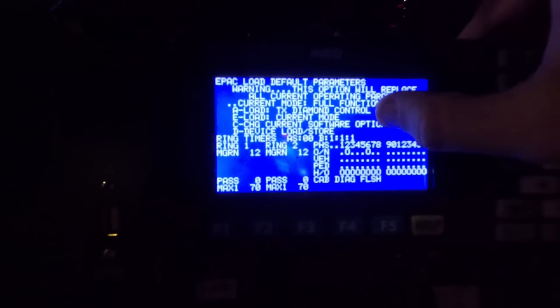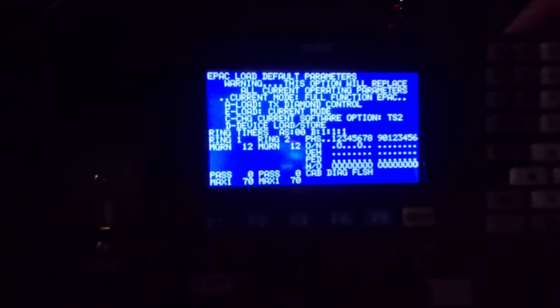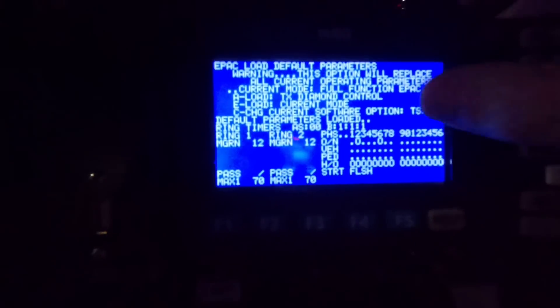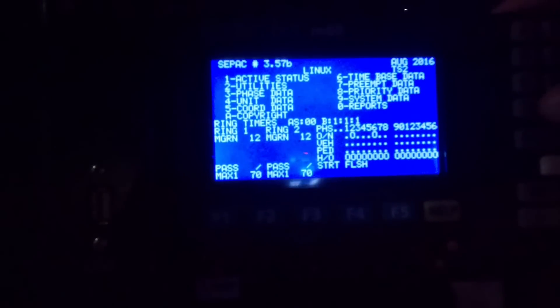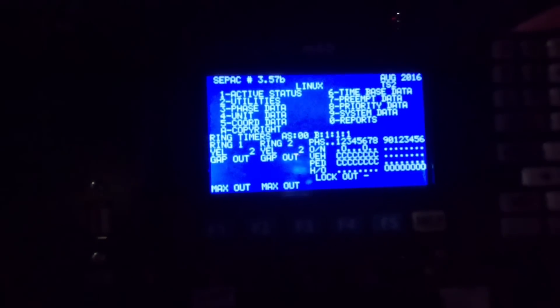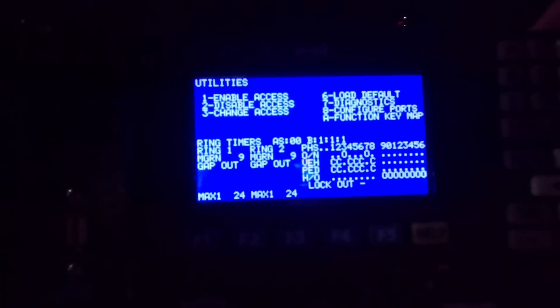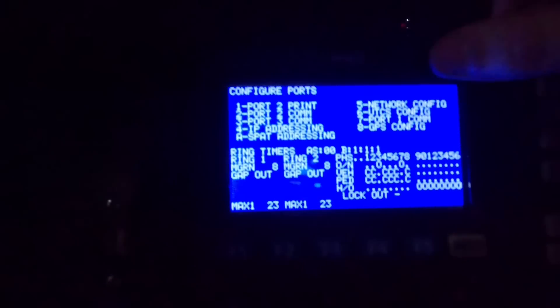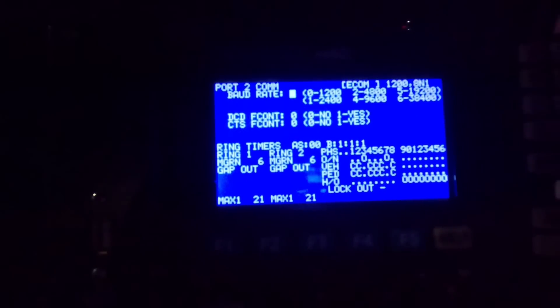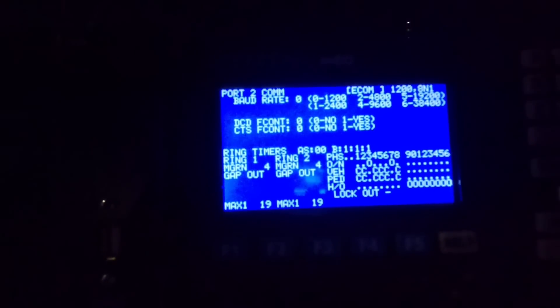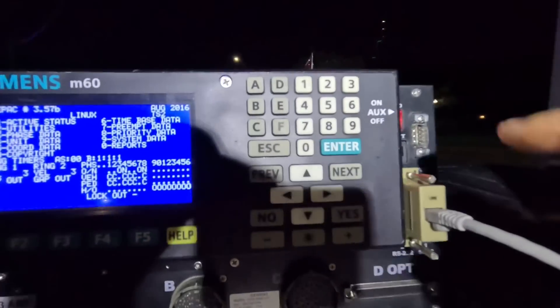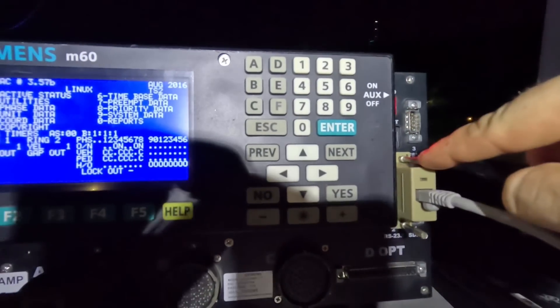I need to press Utilities, you'll see six over here, we're going to hit Load Default, and then Load Current Mode is what we're going to press. If you're enjoying this video, make sure to hit the like button and make sure to subscribe. There we go, the default parameters have been loaded. We can go back out of it. Now we need to hit Utilities, Configure Ports, over here Port 2 COM, and we're going to check A5 right here. That's changing the baud rate of this port right here.